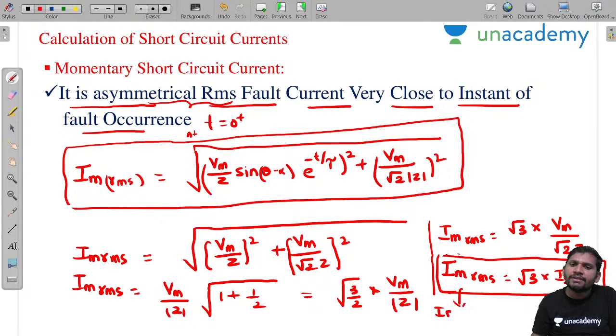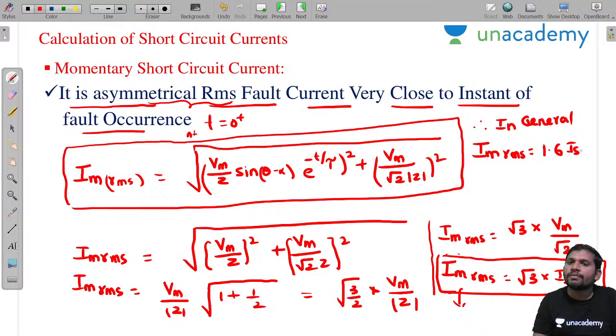In general, this momentary current is taken as follows: instead of root 3, that is 1.732, we generally take 1.6 times the symmetrical current for safety purposes. This is very important, during selection of circuit breakers this calculation matters.